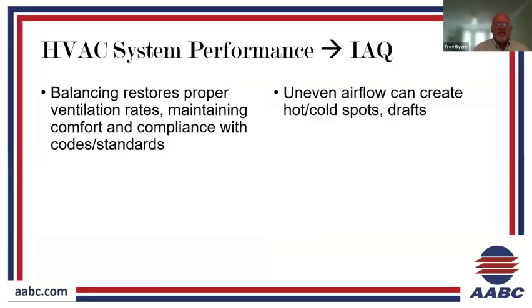So when we think of our system performance and how the HVAC system impacts our indoor air quality, balancing of systems restores our proper ventilation rates, thinking about our outside airflow. That has to do with maintaining our comfort, but also compliance with codes. And so our ASHRAE standards will provide a ventilation rate based on occupancy. Sometimes when we're working with existing buildings, the occupancy of today's building operation and usage is different than when the building was first designed. So that needs to be contemplated. It needs to be reviewed. And obviously we need to measure the current outside airflow rate and then perform balancing to restore the proper rate for today's usage in that building.